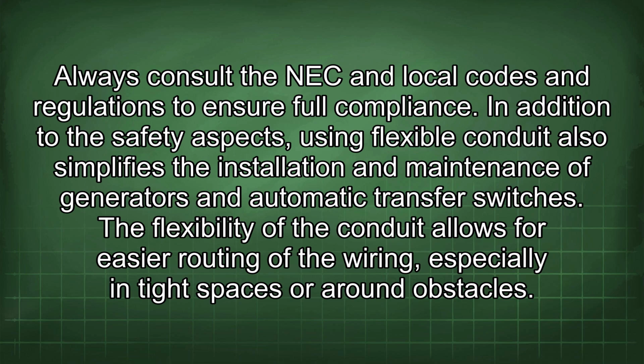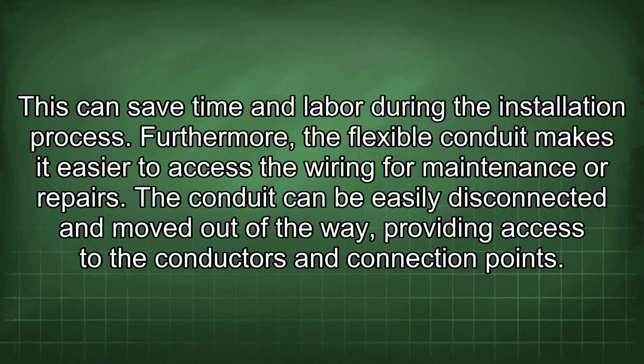In addition to the safety aspects, using flexible conduit also simplifies the installation and maintenance of generators and automatic transfer switches. The flexibility of the conduit allows for easier routing of the wiring, especially in tight spaces or around obstacles. This can save time and labor during the installation process. Furthermore, the flexible conduit makes it easier to access the wiring for maintenance or repairs.